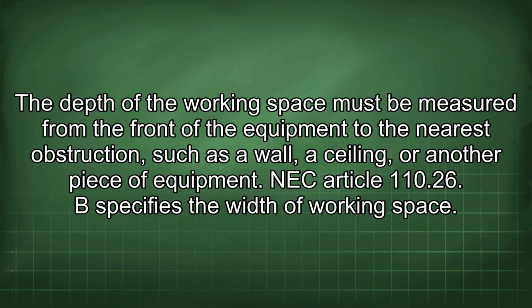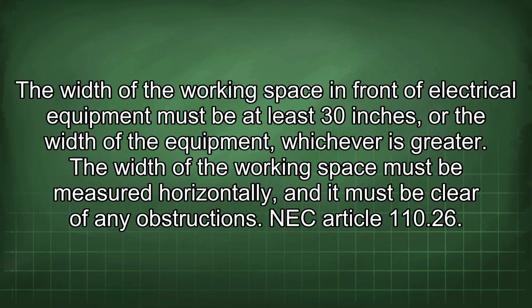NEC Article 110.26 B specifies the width of working space. The width of the working space in front of electrical equipment must be at least 30 inches, or the width of the equipment, whichever is greater. The width of the working space must be measured horizontally, and it must be clear of any obstructions.